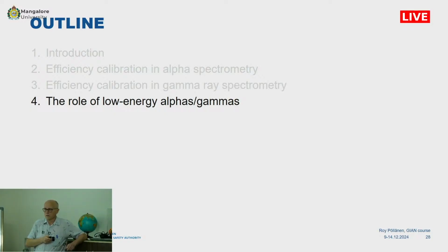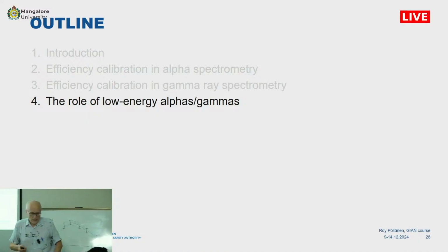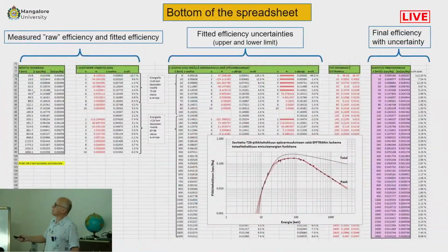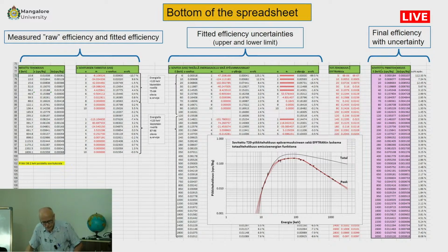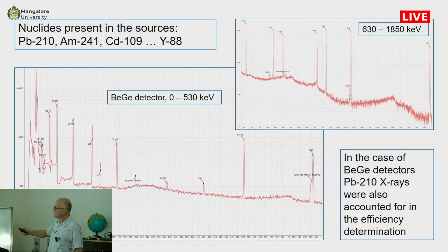So, in one of the efficiency graphs, you showed the peak curve and then a total curve. Yeah. So what is a total curve? Total count, that one, yeah. Total count, the so-called total efficiency. It takes each count of the whole spectrum into account, and it is used for the coincidence correction calculation.